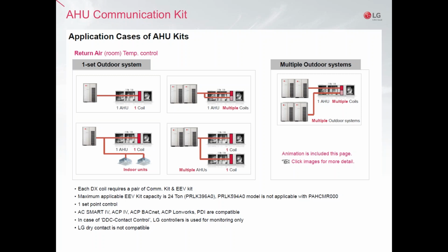Now, with the return air controller, we have some interesting features not available in the supply air control. We can have additional indoor units connected to the same refrigerant piping system, which could be LG VRF indoor units, like in the bottom left. You can see there that we have a single condenser that could be connected to the air handling unit in a single coil, and you have a branch that goes to two indoor units. And we can also have it connected to another third-party air handling unit, also operating as a return air temperature control. As you can see here, we have two condensers connected to two different coils in a single circuit. So they will be operating like two different units.